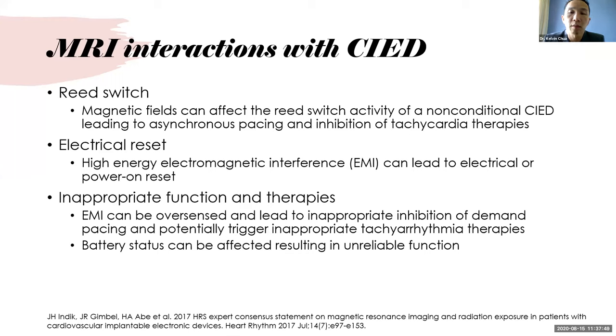The reed switch is used by a device for programming by placement of a magnet. Magnetic fields can affect the reed switch activity, especially on a non-conditional device, leading to asynchronous pacing and inhibition of tachycardia therapies. There can also be electrical resets because high energy electromagnetic interference, what we call EMI, can lead to electrical or power-on reset where pacing might be inhibited and tachyarrhythmia therapies activated.